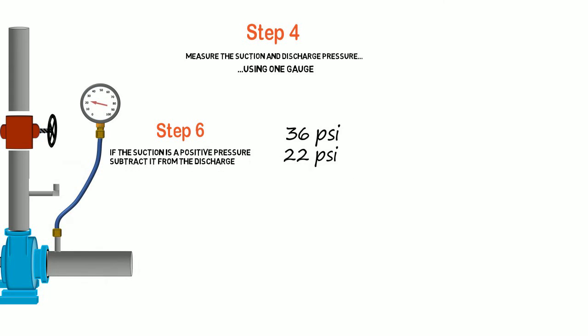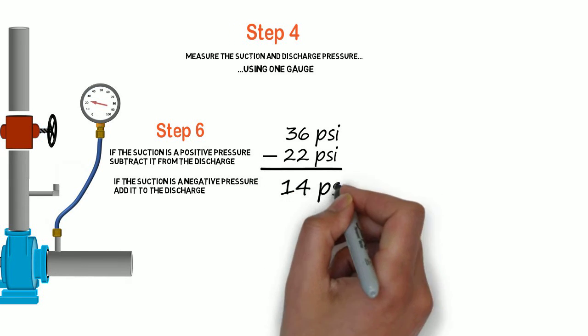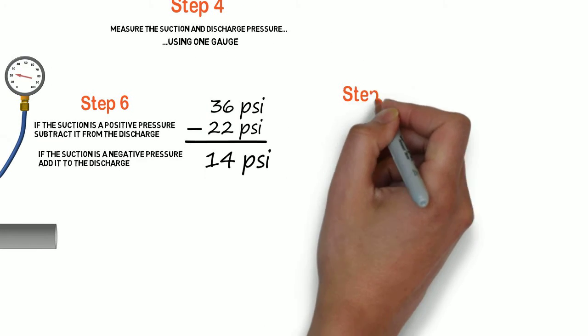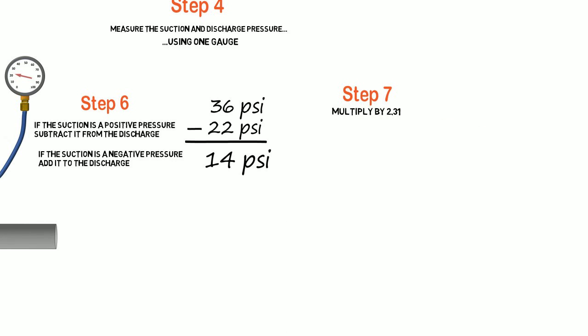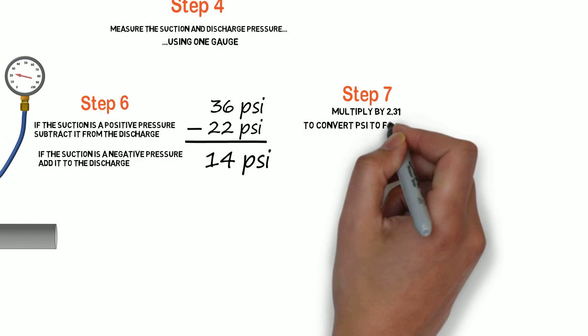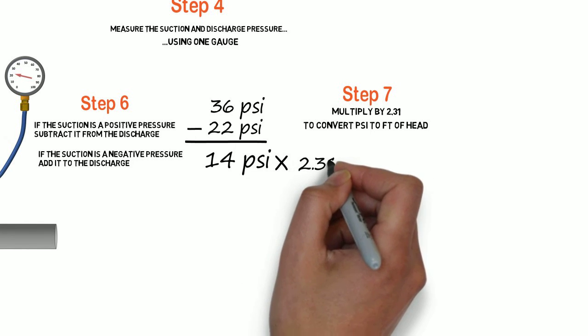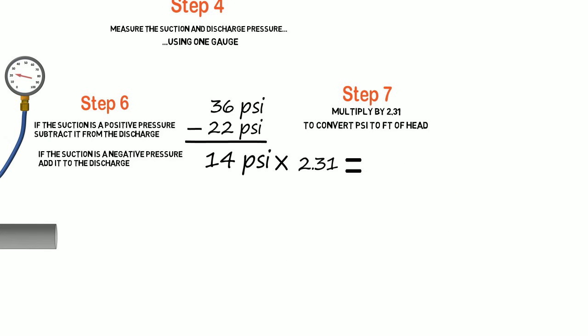Step six, if the suction was a positive pressure, we're going to subtract it from the discharge. If it was a negative pressure, we're going to add it. In our case, it was a positive, so we're going to subtract it. So 22 from 36 is 14 psi. Write it down. Now we have to convert psi to feet of head. We do that by multiplying it by 2.31. So 14 times 2.31 equals, drumroll, 32.34. We'll call it 32.